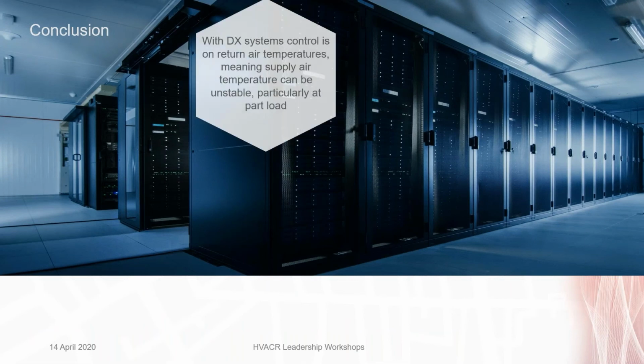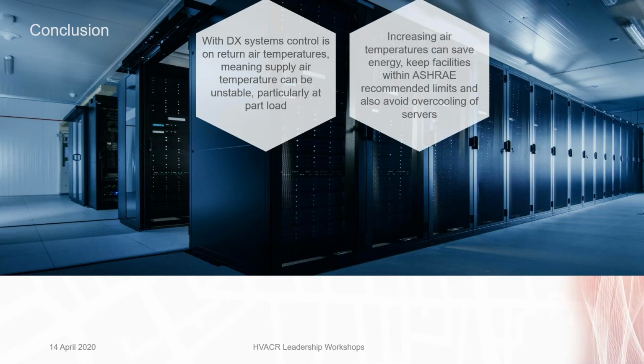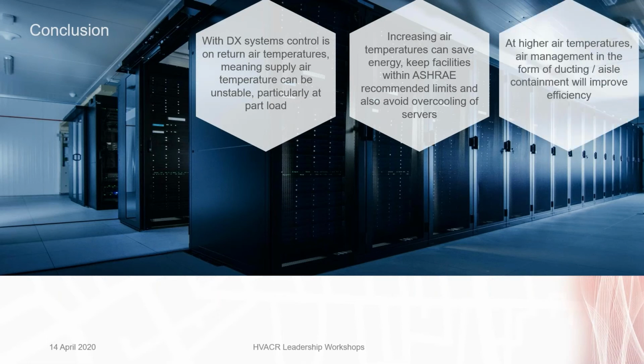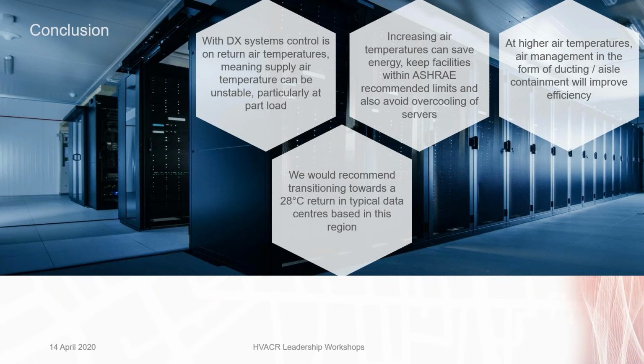As DX systems are return air controlled, the supply air temperature can be unstable, particularly at part load where we're using multiple or tandem compressors. Increasing air temperature can save energy, keep facilities within ASHRAE recommended limits, and also avoid overcooling of the servers. At higher air temperatures, air management in the form of ducting or aisle containment will definitely improve efficiency. So we would recommend a transition towards a 28-degree return air in a typical data center in this region, where we now see a 20-degree set point. We strongly recommend a transition towards 28 degrees.